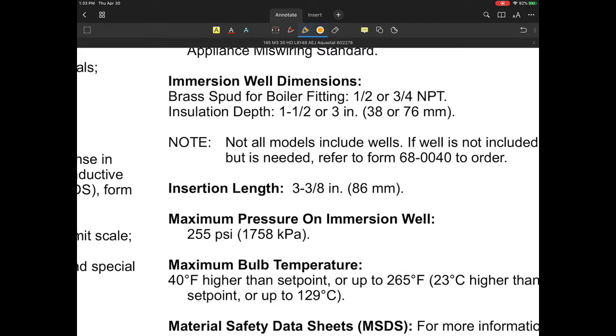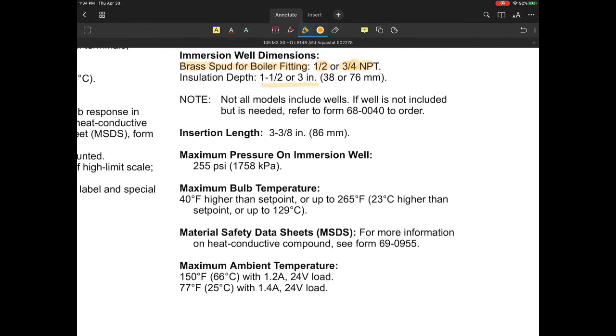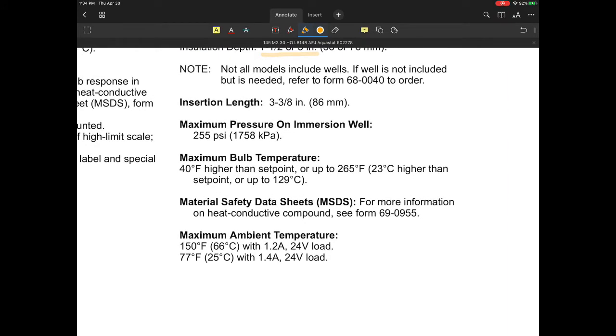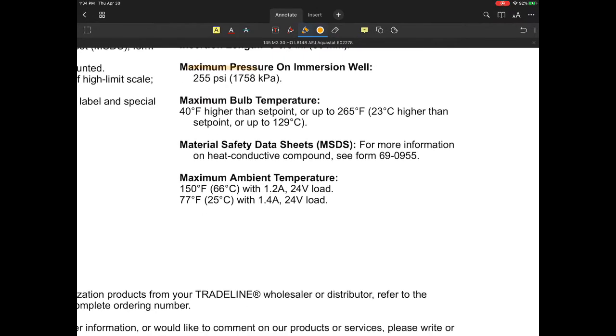So the immersion well. Along with these Aquastats, they will bring you what they call a brass insert, what they're calling an immersion well. Typically it's either going to be a 1/2 inch or a 3/4 inch pipe thread. This is not something you should ever have to change. It's completely part of the boiler system. So if you have an Aquastat that goes bad, you're likely going to just change the Aquastat and use the existing well. The insertion depth they're identifying as 1.5 to 3 inches is really how far it's inserted into the system. All right.